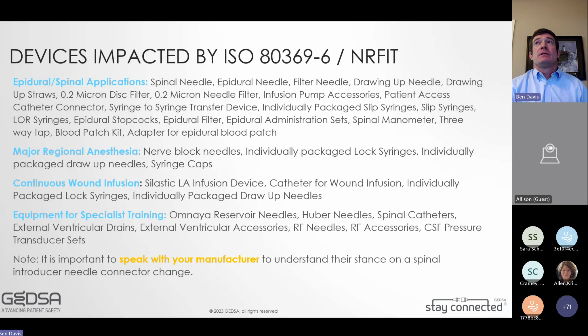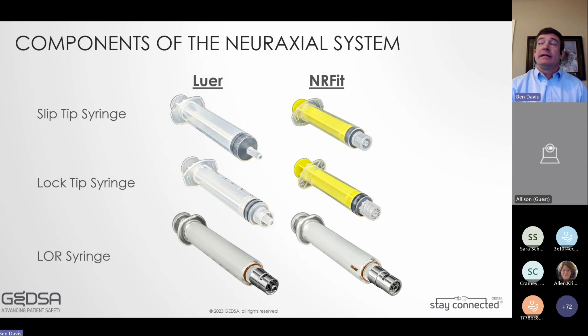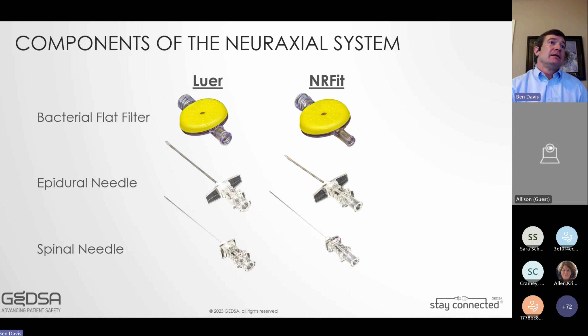There's also the locking syringe. So you have a Luer lock, and it's just shown in that video, the NRFit lock, the nozzle does not protrude past the collar. Then you have your loss of resistance syringes, and same thing, you can see how the nozzle does not protrude past the collar on the NRFit version there on the right. You also have bacterial flat filters. The previous slide was all male connectors. This slide just happens to show all female connectors. You can see that the Luer is a little bit larger than the NRFit connectors on the right.